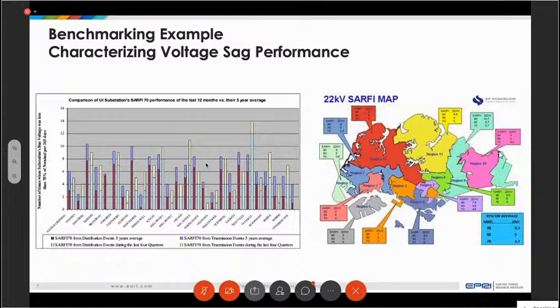We use an index called SARFI, or the System Average RMS Variation Frequency Index. So if we say SARFI 70, that means this is the number of times that a voltage sag went below 70% voltage at a particular location.